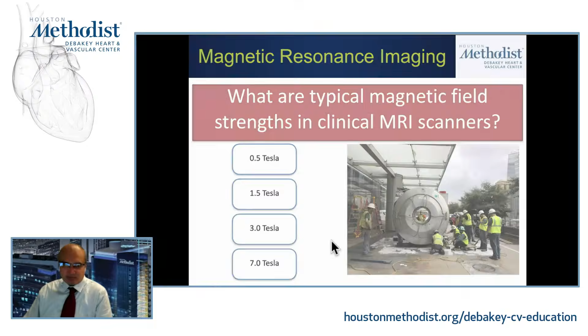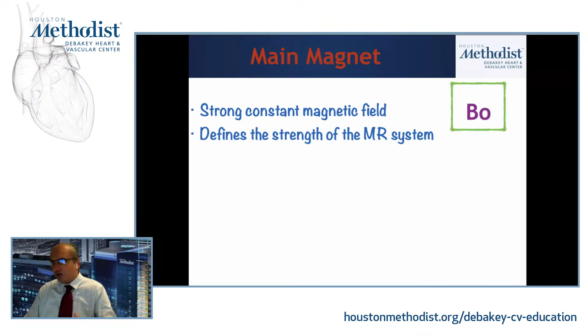So, a couple of things about the main magnet. It's a strong, constant magnetic field, and really it defines the strength of the MRI system. So you can't go from a 1.5 to a 3T. You have a scanner and it's either 1.5 or 3 or 0.5 or whatever it is. Now there are some hardware versions which allow you to ramp up or ramp down a magnetic field. But again, that's an extensive process to go from a 1.5 to a 3 or 3 down to 1.5. But in general, whatever magnetic field you have is what you have.